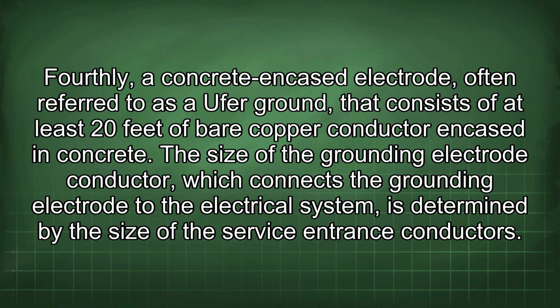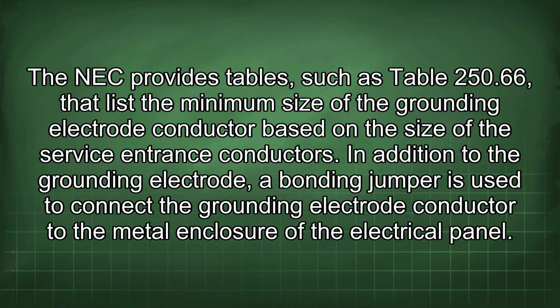The size of the grounding electrode conductor, which connects the grounding electrode to the electrical system, is determined by the size of the service entrance conductors. The NEC provides tables, such as Table 250.66, that list the minimum size of the grounding electrode conductor based on the size of the service entrance conductors.